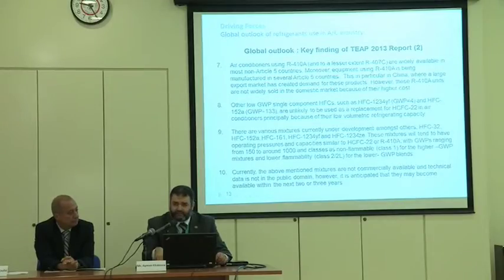410A is apparently still dominant in most developed countries. R407C is losing ground and almost phasing out from most of the air conditioning industry, except in a few developed countries. Article 5, or developing, countries already have the capacity to introduce 410A, but were not doing so because R22 was still allowed in most of them. So manufacturers produce 410A only upon request by local markets or for export to non-developing country markets.